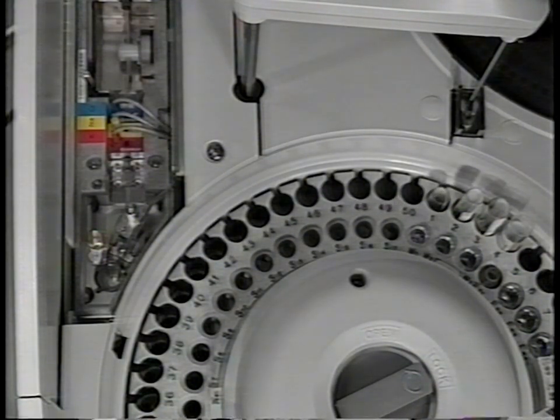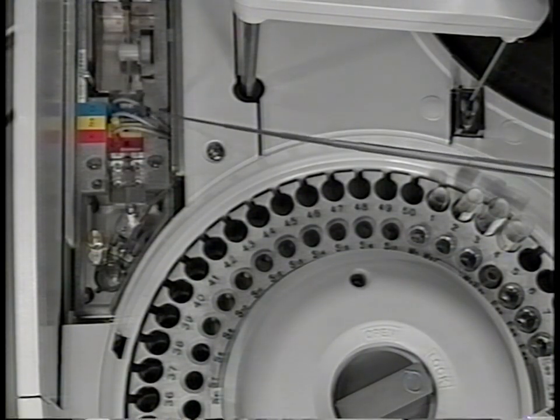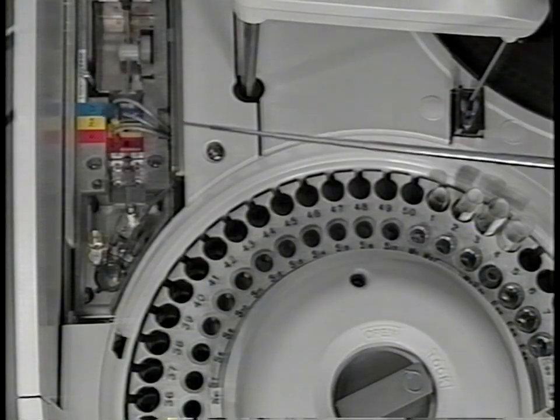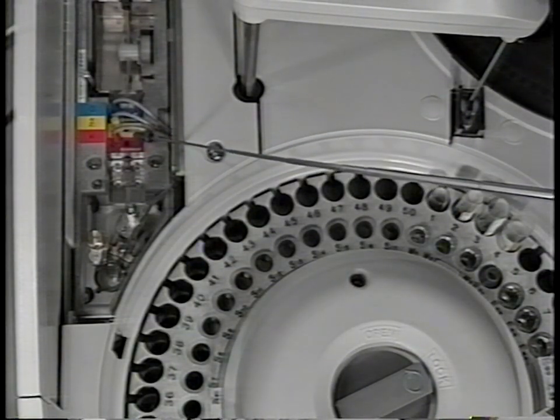The actual ISE measurements are made inside 3 ISE cartridges. They are color-coded for easy identification. The chloride cartridge is blue, the sodium cartridge is yellow, and the potassium cartridge is red. The ISE cartridges measure the electrical potentials of sodium, potassium, and chloride ions in diluted samples. The potentials are then used to calculate ion concentration in the samples. The ISE compartment is temperature controlled. This helps to ensure precision of ISE measurements.